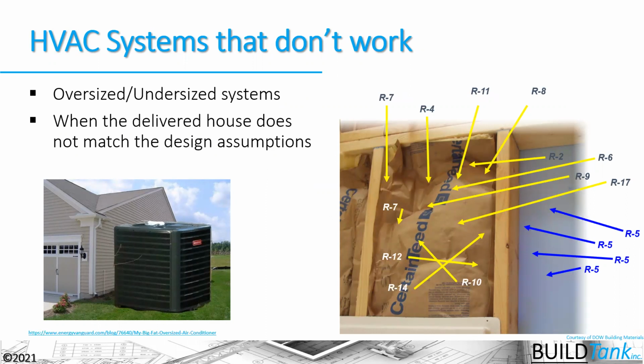So for example, if I designed and developed the load in my manual J for a house that I assumed had an R19 batt in the exterior walls, and that batt was clearly compressed in its installation, and it was really achieving an R7 instead of an R19, well, my system was probably going to be undersized and not work properly there. And we might see that the HVAC contractor is going into the process assuming that the thermal envelope isn't going to be executed well, and therefore they're trying to compensate for that by manipulating the manual J in some way to oversize the equipment there.